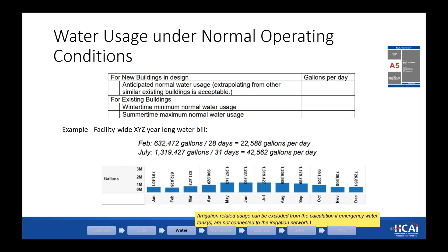Not all facilities have water meters at multiple locations. Most facilities have only one water meter, so it becomes hard to distinguish the water usage between different buildings, or even, if you have a non-acute care building on the campus, how much water that uses. So there will be work needed after, but this is a good place to start from. We highly recommend looking at the water bill first. Another item to look for is irrigation demand. Again, if you have a shut-off valve, this demand can be easily reduced in your emergency operation plan.